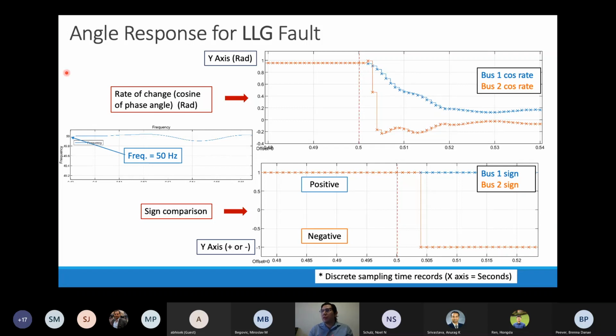So here we tested the line to ground fault. And as we can see, when the double line to ground fault happens, I'm showing the rate of change in the cosine function on the upper figure, and on the bottom I'm showing the sign comparison, which is the sign of the cosine of the angle that we were measuring in the upper figure. Our grid frequency is 50 Hertz, and these are measured just in the line that is talking with both ends, the one I presented a few slides before. The blue line represents the bus 1 end, and the orange one represents the bus 2 end.